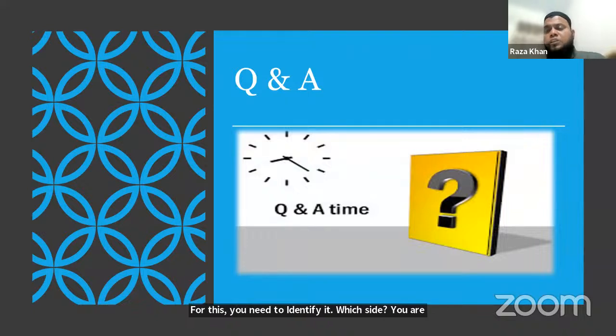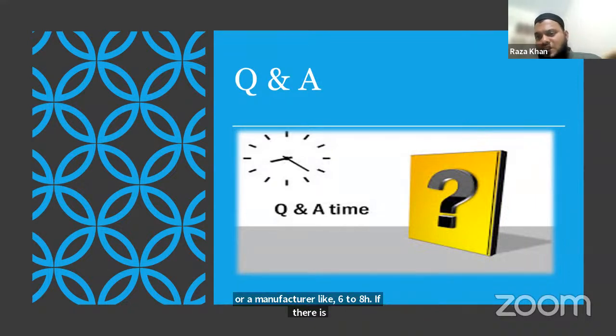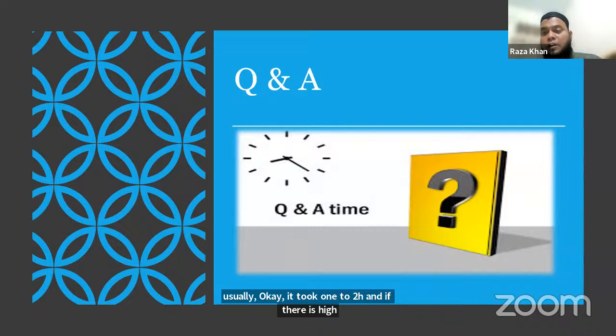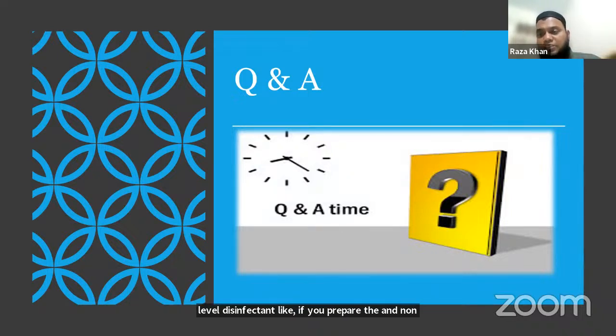If the dilution is high, we can label this type of solution as a low level disinfectant, LLD. For this, the instrument usually needs prolonged hours of exposure as per the recommendation of the agent or manufacturer, like 6 to 8 hours. If there is an intermediate level disinfectant, then usually it takes 1 to 2 hours. And if there is a high level disinfectant, like if you prepare the glutaraldehyde solution and non-glutaraldehyde solutions in a concentrated way, then the required exposure time is less, like 15 to 30 minutes. So it depends on the manufacturer guidelines.